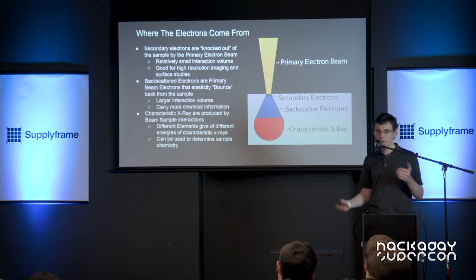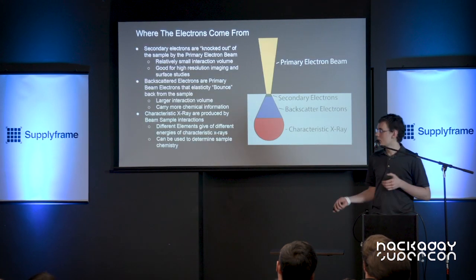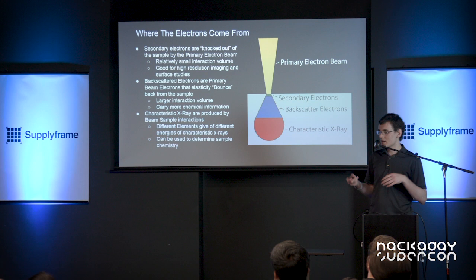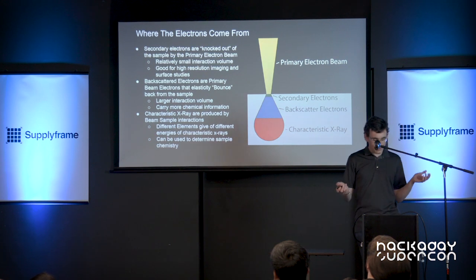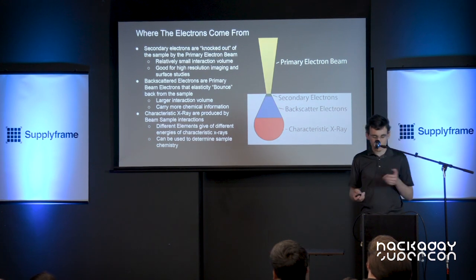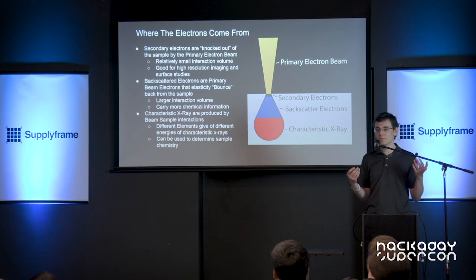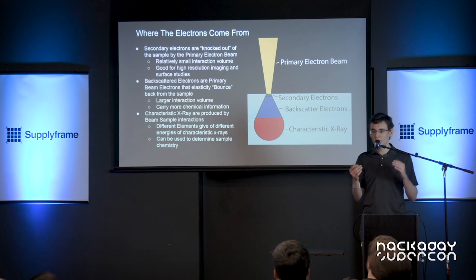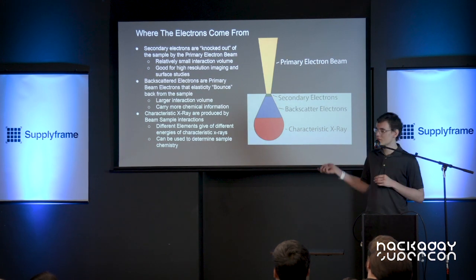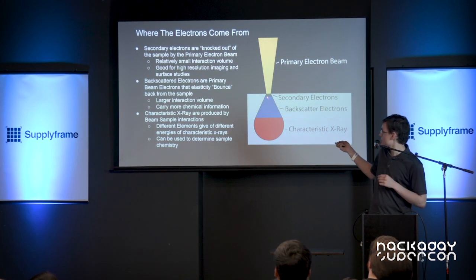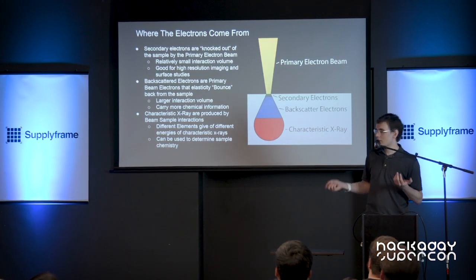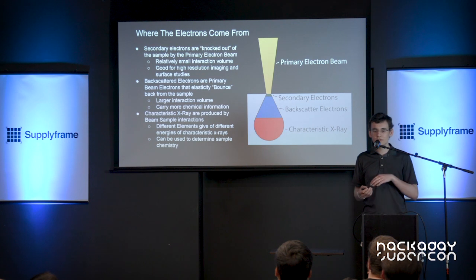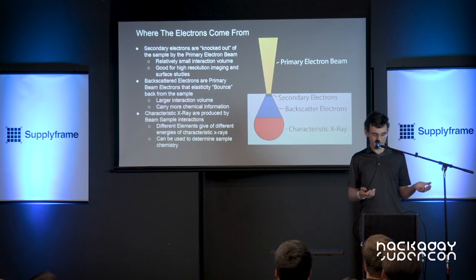Let's talk about where the electrons come from in an SEM. We start with secondary electrons. Secondary electrons are knocked out of the sample by the primary beam. They come from the surface of the sample and from a relatively small interaction volume, so they're very high resolution and really good for studying the surface of a sample.